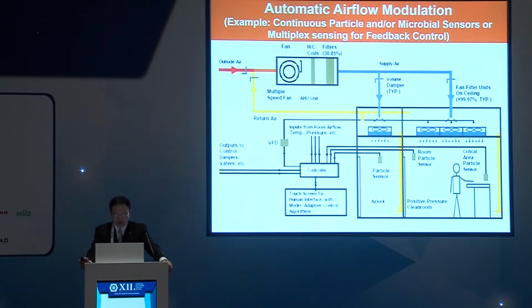This is a very simple flow diagram to illustrate how to control the room particle concentration or room cleanliness level through typical AHU level control. In this case, you may have two rooms, an airlock room and a clean room. You can have multiple real-time particle sensors, typically laser. And you may have a controller. You also have a variable speed drive in order to modulate the speed of the fan filter units. So once this particle sensor says my room is already ISO class 5, then you don't need to speed up the fan.